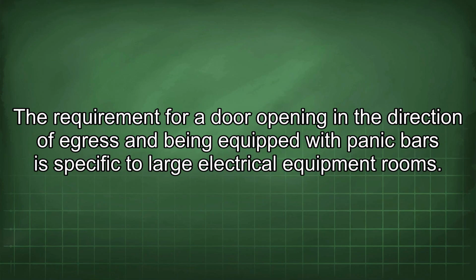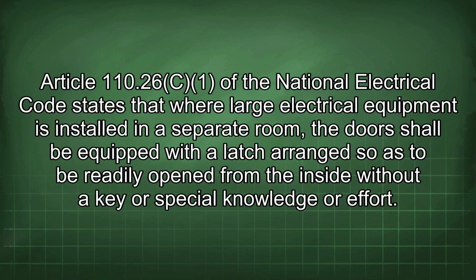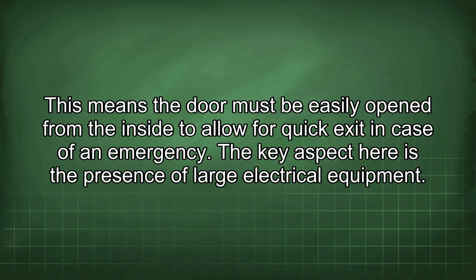The requirement for a door opening in the direction of egress and being equipped with panic bars is specific to large electrical equipment rooms. Article 110.26(C) of the National Electrical Code states that where large electrical equipment is installed in a separate room, the doors shall be equipped with a latch arranged so as to be readily opened from the inside without a key or special knowledge or effort. This means the door must be easily opened from the inside to allow for quick exit in case of an emergency. The key aspect here is the presence of large electrical equipment.